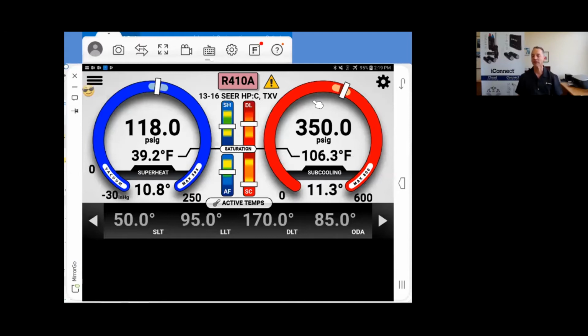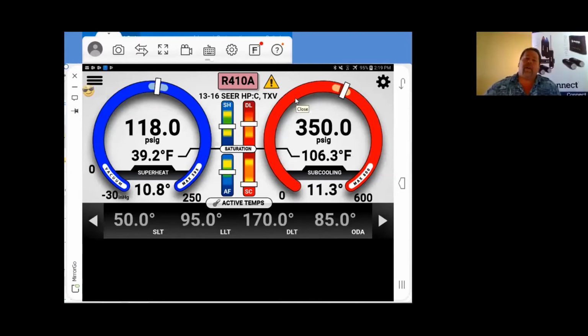Is that a must? Now, if you're working on low temp systems, either way, on air conditioning or that, it's not a necessity. Discharge line temperature, we use it mainly for troubleshooting. With high discharge line temperature, there'll be a restriction that's causing that. You got low discharge line temperature, you've got liquid refrigerant going through, bad valves or something like that. But it's definitely not a necessity to be using it. It aids in troubleshooting, definitely.